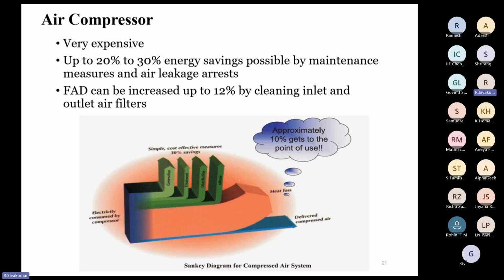So the air compressor is very expensive, and 20 to 30% energy saving is possible by adopting some maintenance measures and fixing air leakages. Air leakages are a very important aspect of energy saving measures in air compressors. So it should be a routine practice: every alternate month or every month, do the air leakage test and arrest all the air leakages, because they consume more energy. The FAD, which is called free air delivery, can be increased up to 12% by proper maintenance, including cleaning the inlet and outlet air filters.